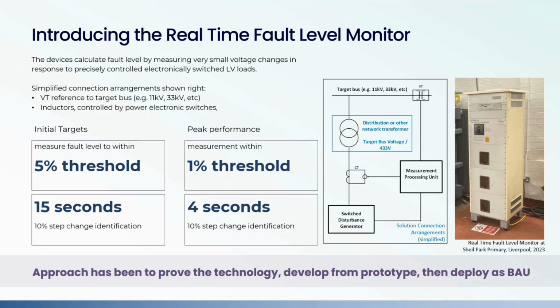And the device itself is modular in the way it's constructed. There's three bottom racks or trays, and they have banks of low voltage inductors in them. Then the next tray up contains the power electronic switches and protection devices. And then the two trays above that contain the main processor unit and the comms rack for interfacing with our SCADA to allow us to take the real-time measurements through to our SCADA system, so our control engineers have access to it in the control room.